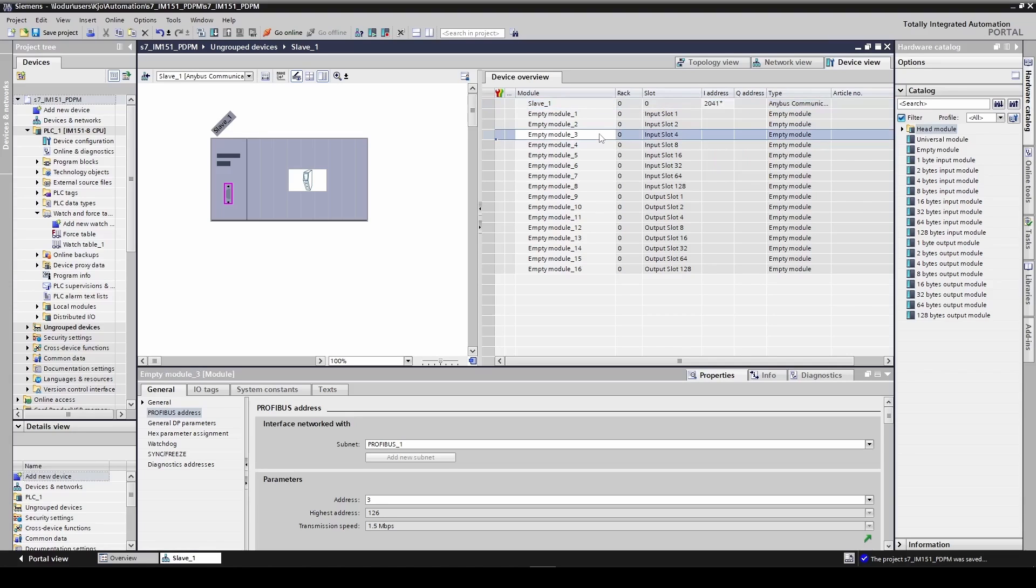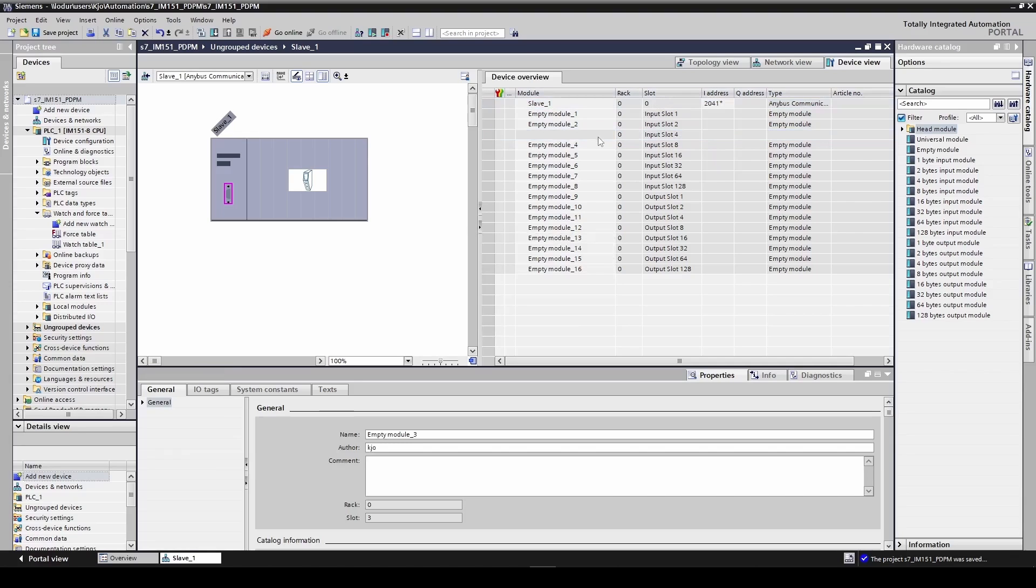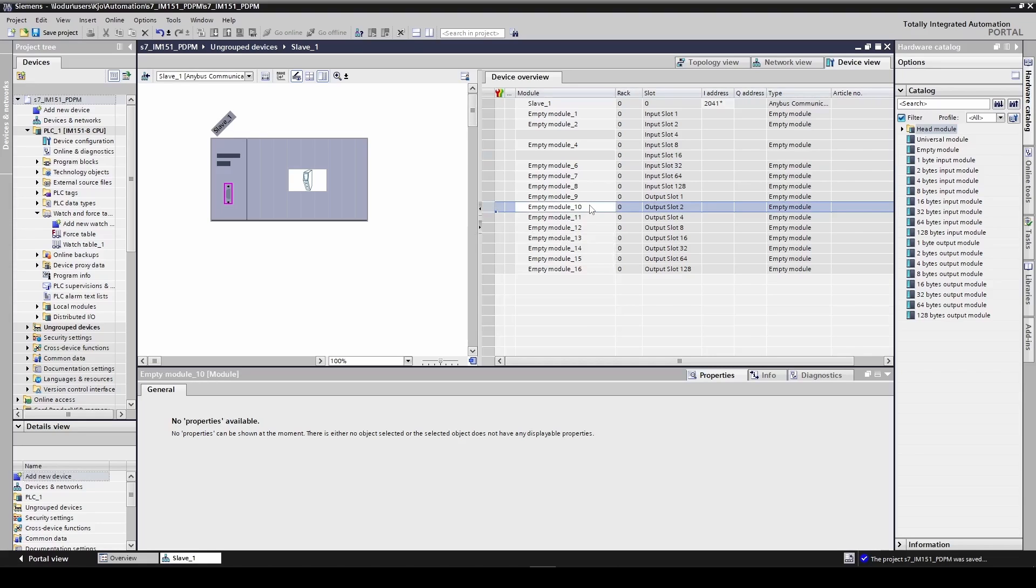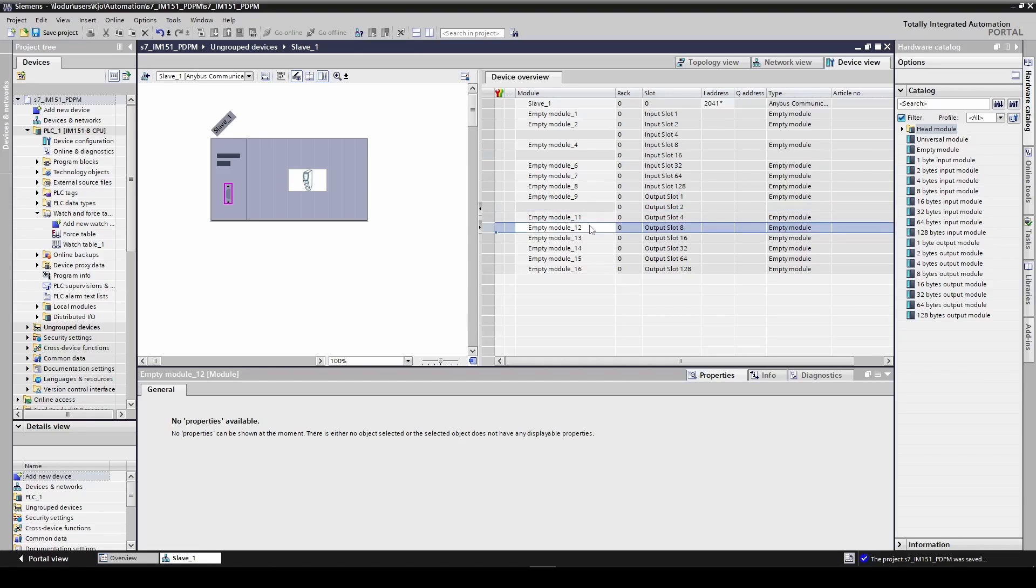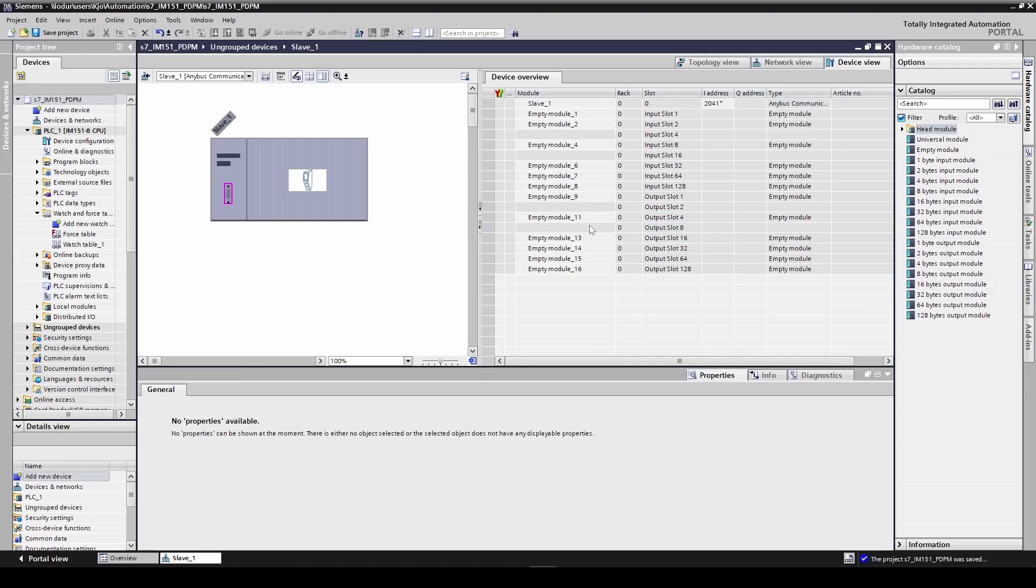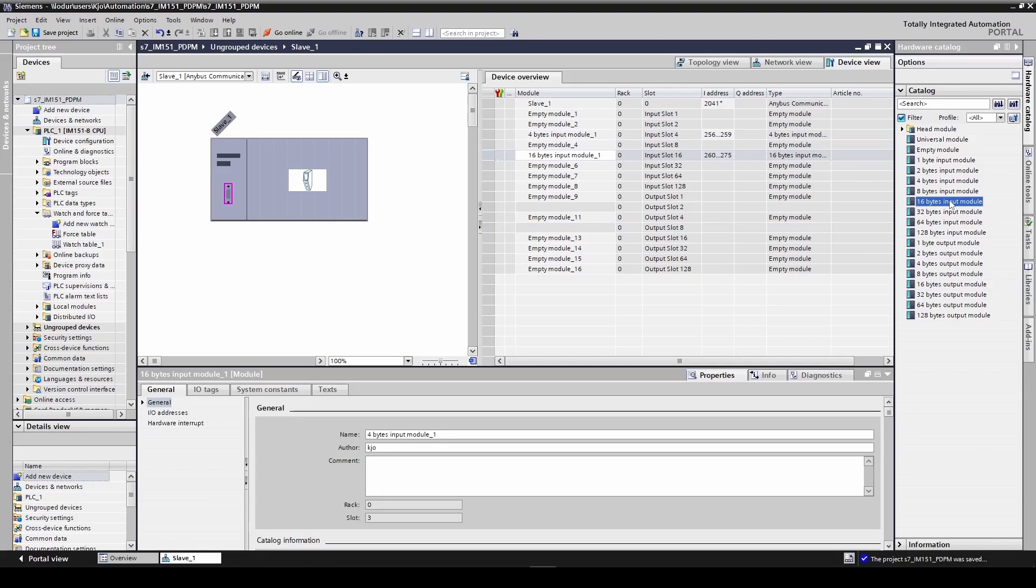I first delete these empty modules occupying these slots. I then double click each module and it will automatically occupy the correct module slot. The order does not matter. First the 4 byte input module, then the 16 byte input module, followed by the 2 byte output module and the 8 byte output module.